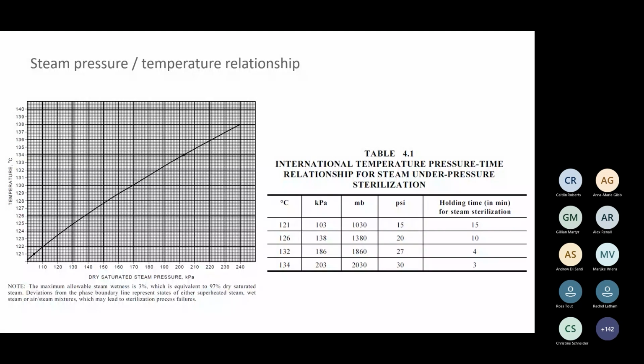This graph is in the Australian standard, so it's very easy for you to find it. Generally, most sterilizers are set for 134 degrees with about a 3.5 minute holding time. Most of your MELAGs hold for 5 minutes. So you will still be safe. If your machine drops below 134 or down to 132, and you're holding for 5 minutes, your load is definitely processed and safe to use.